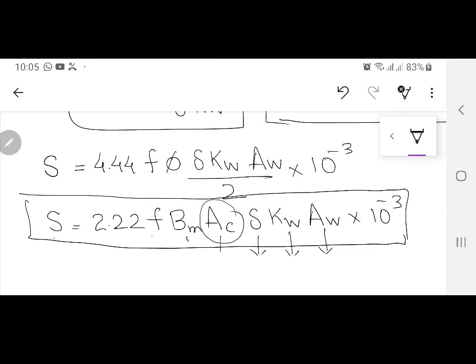And which area is this? For example, if I am talking about a shell type transformer, the central limb inside this transformer, its cross sectional area, which I am seeing from the top. Please remember this thing, the center area will be double than what you are seeing over here on this side or this side. Why double? Because half of the flux goes here, half of the flux goes here. So to keep the flux density same in the outer legs, the area of the central limb in this shell type is double as compared to the outer two limbs. Okay. Any questions with this?